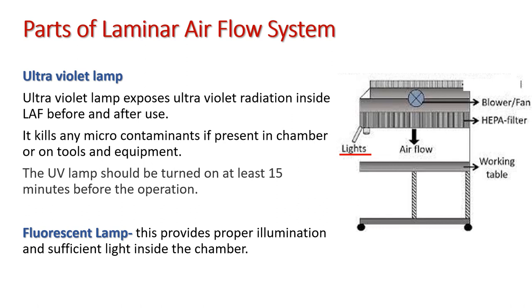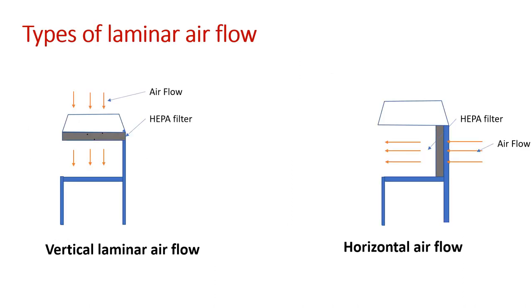The ultraviolet lamp exposes ultraviolet light radiation inside the LAF before and after use. It kills any micro contaminants present in the chamber or on tools and equipment. A UV lamp should be turned on at least 15 minutes before operation. The fluorescent lamp provides proper illumination and sufficient light inside the chamber.